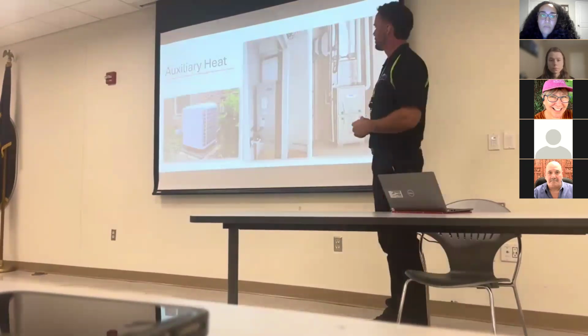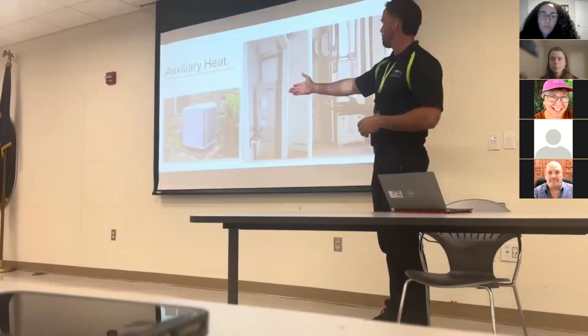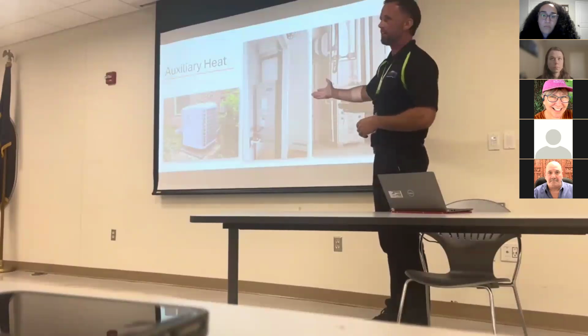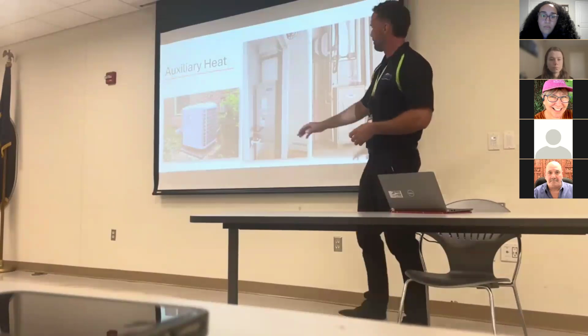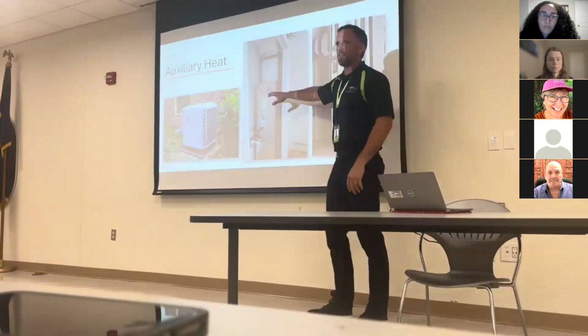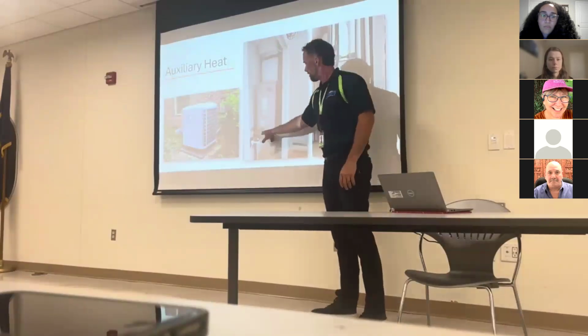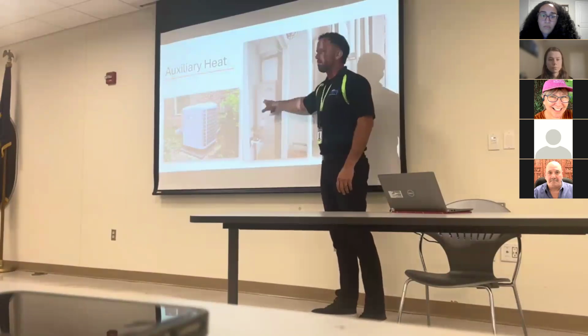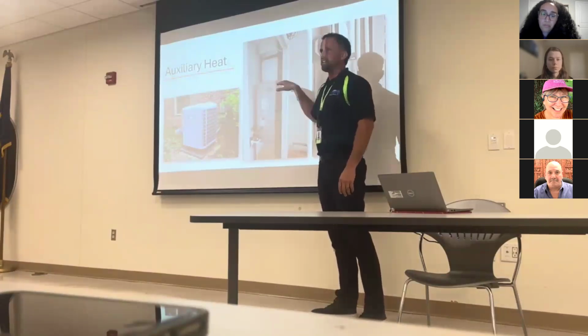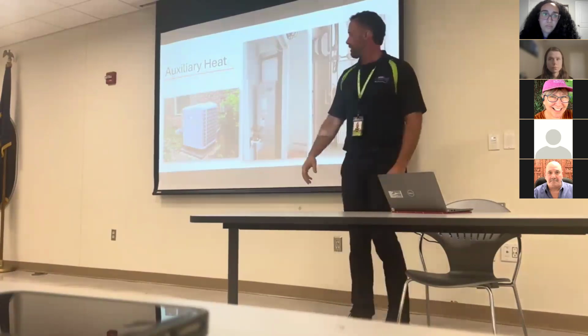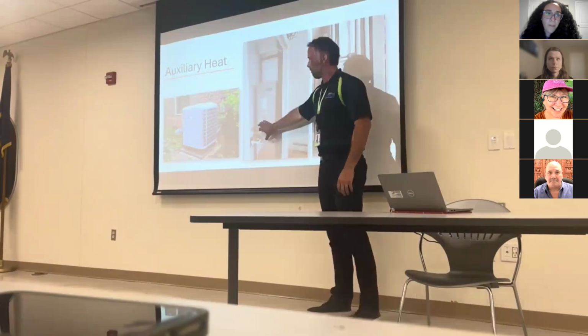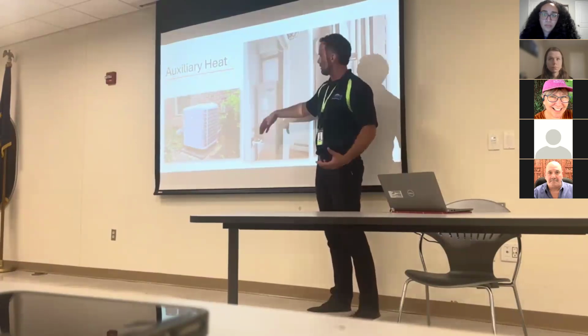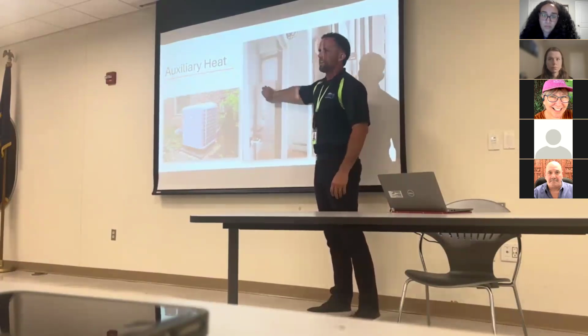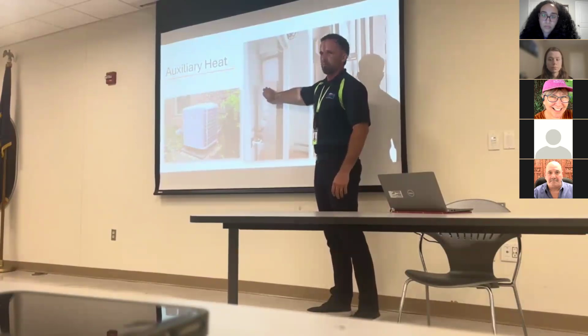A little more about auxiliary heat. Like I said, your heat pump can be paired with electric backup heat or gas. So this is an electric furnace. We call it an air handler. It's got the indoor coil there, it's got a blower up here, and electric heat banks can be installed up here to be the auxiliary heat. The heat pump would be the primary source, where this coil gets nice and hot, but then after that, the auxiliary heat comes on and the electric heat banks would kick on up here.